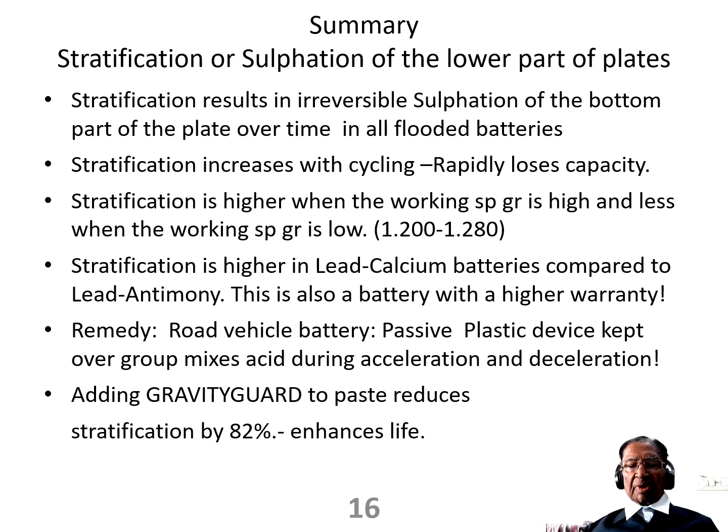Stratification is higher when the working specific gravity is high, and less when the working specific gravity is low. Stratification is higher in lead calcium batteries, mind you, compared to lead antimony. So this is a battery with a higher warranty and a higher price. Naturally, you must introduce the chemical or the plastic mixing device in all lead calcium batteries, the higher end batteries.